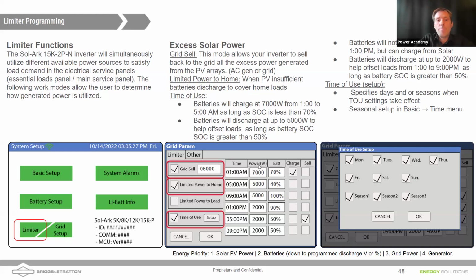So you can also set up here a sell option. If you wanted to sell excess power to the grid, you could control output of the batteries between the hours of 5 p.m. and 9 p.m. And as long as the batteries are above a 50% state of charge, we'll discharge them at 2,000 watts back to the grid. We have a question, Nathan.